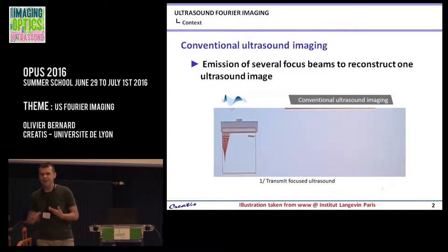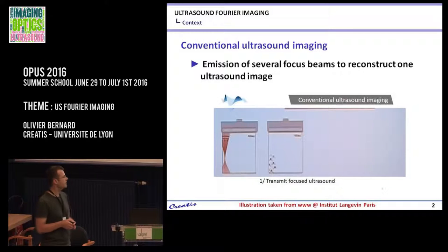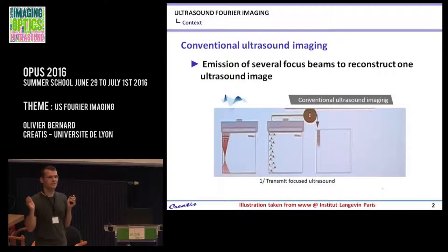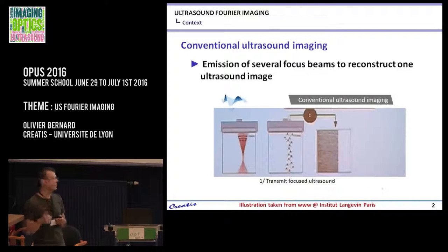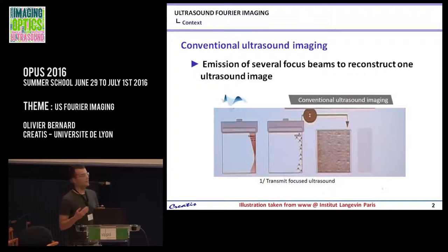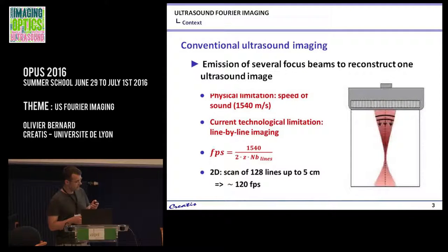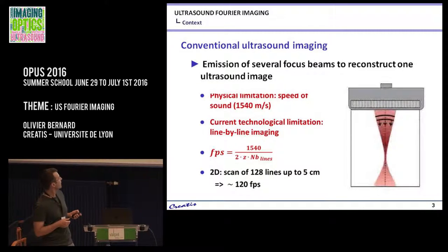I will not go again with this ultra-fast acquisition convention. I consider that you understand it. So in the classical way, you focus and repeat, so you can sweep each time of your image. And of course, you have to wait for the time that your wave comes back before firing the other one. And this limits the frame rate that you can have.